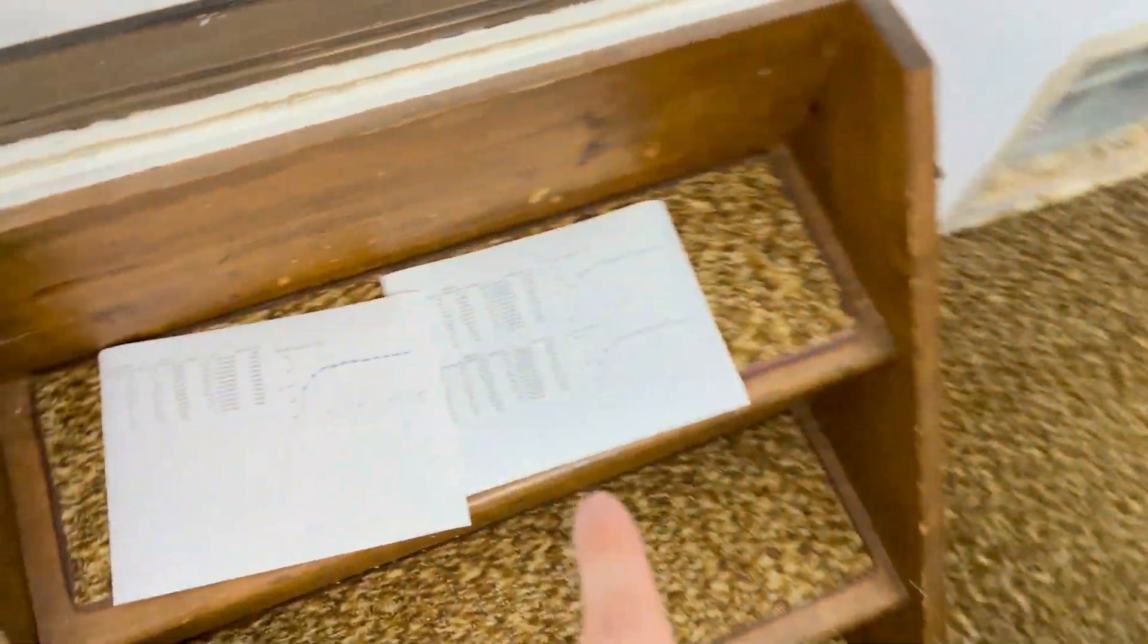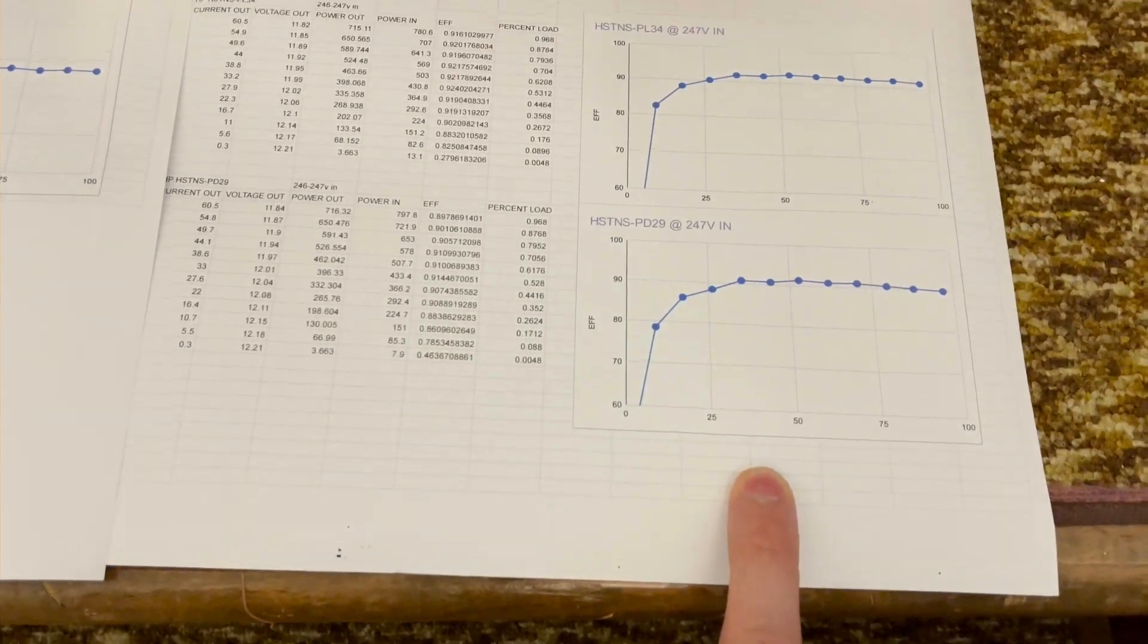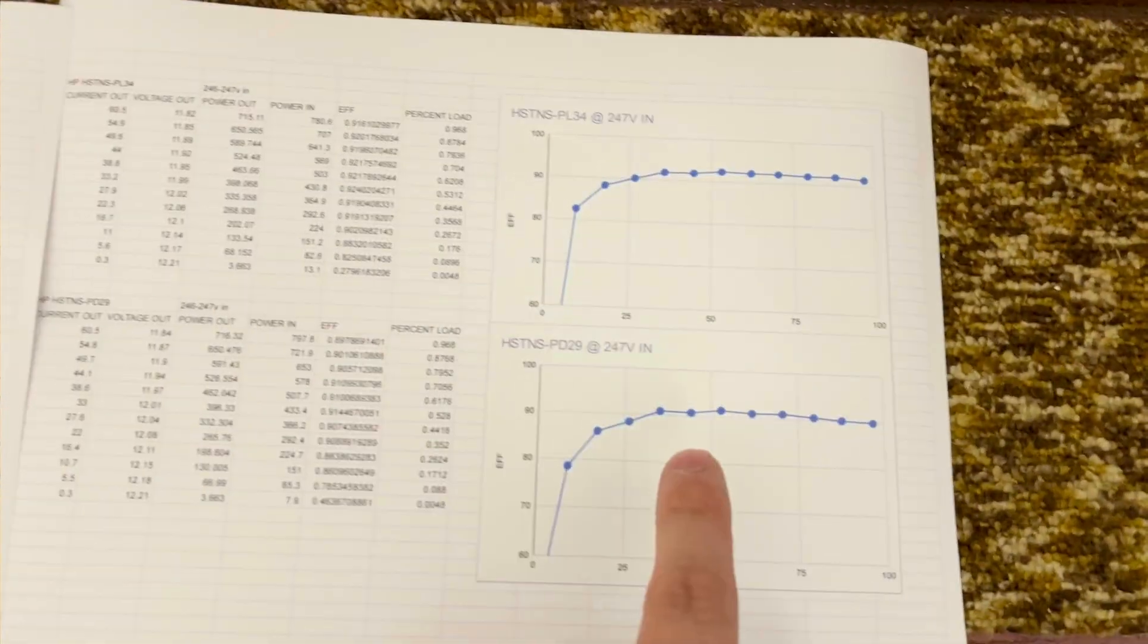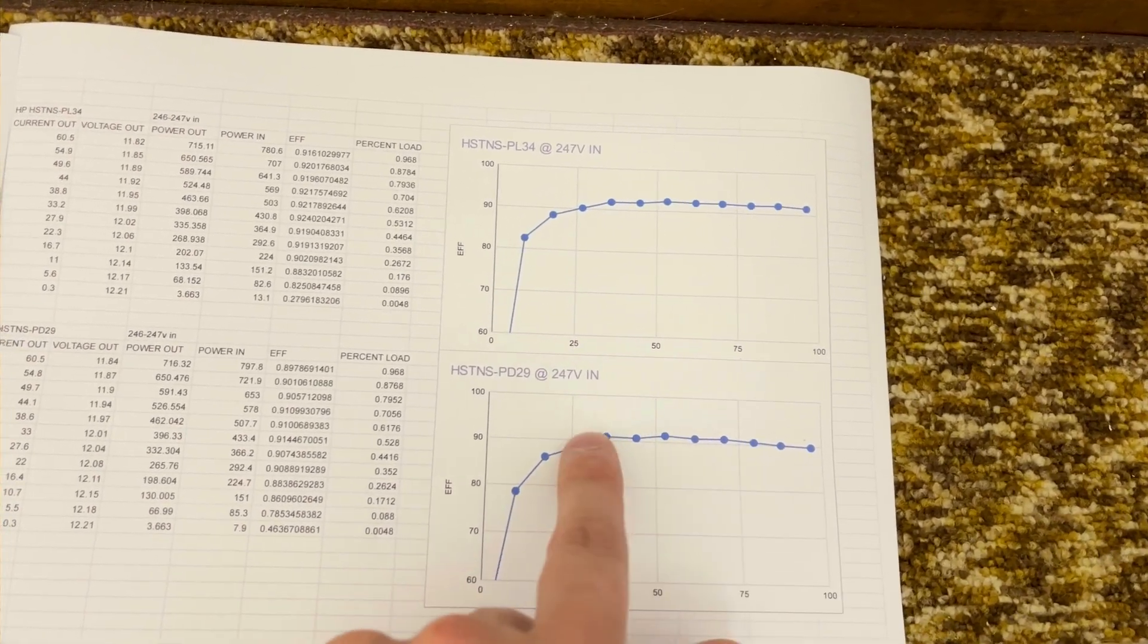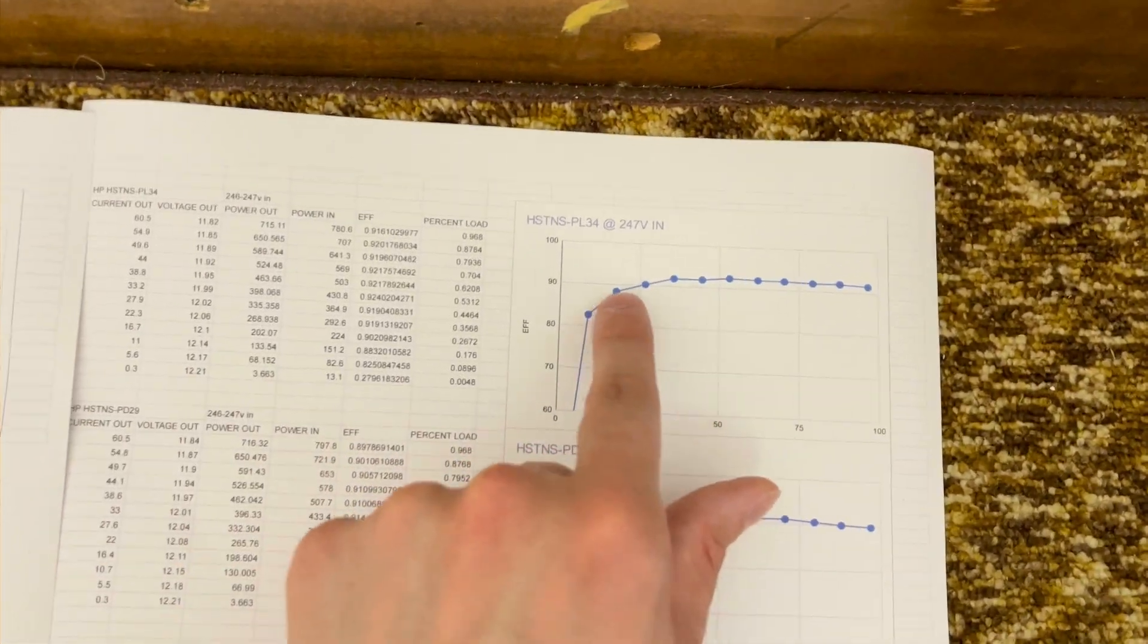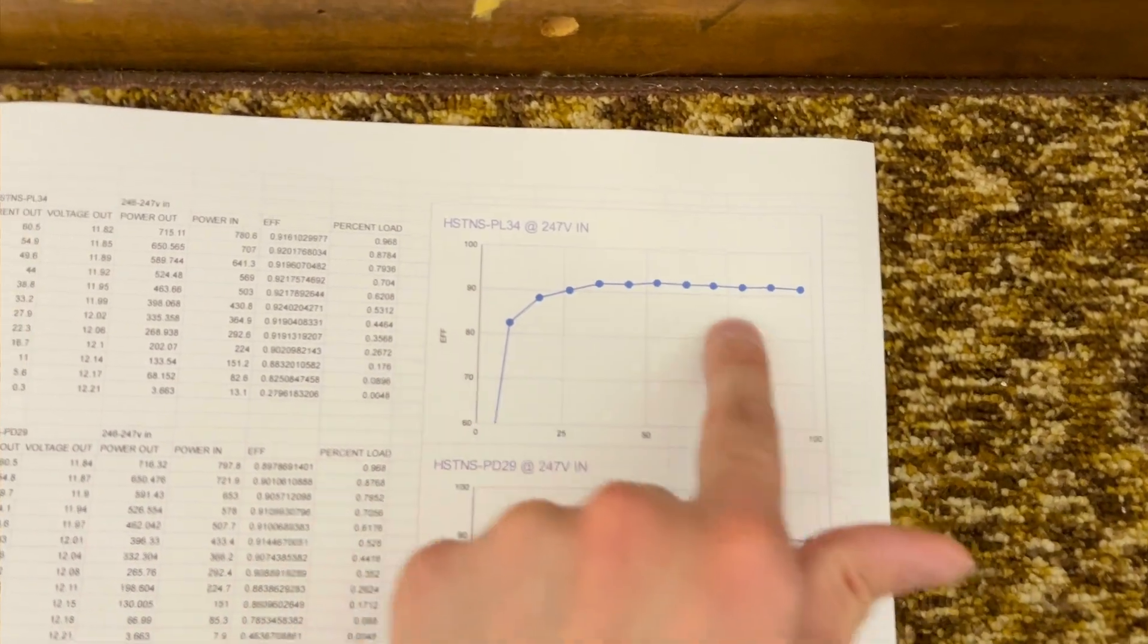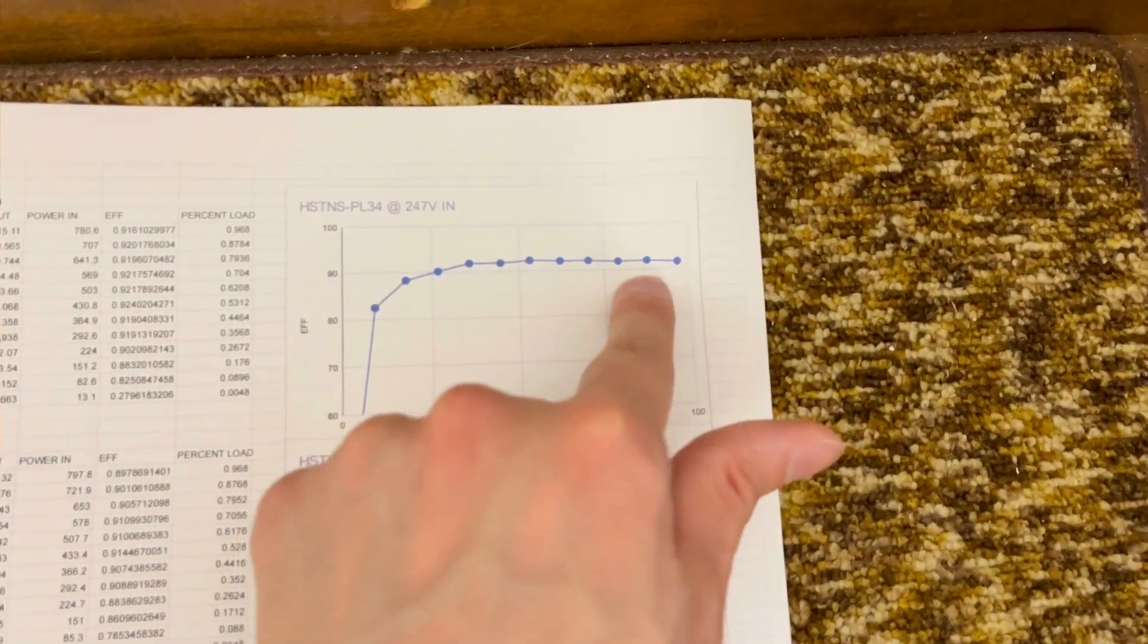Typically, power supplies are most efficient around 50% load, but this is going to depend on the power supply. So here's data that I calculated with my common power supplies, the HSTNS PD29, HSTNS PL34. And you can see the data here. This one peaks at around 60% or so, plus or minus. You can see it goes up and it comes back down a little bit. This one has a flatter curve. It stays higher for longer. This one matters less for loading. As long as you're above, say, 35% or so, it's efficient all the way up to 90-95%.